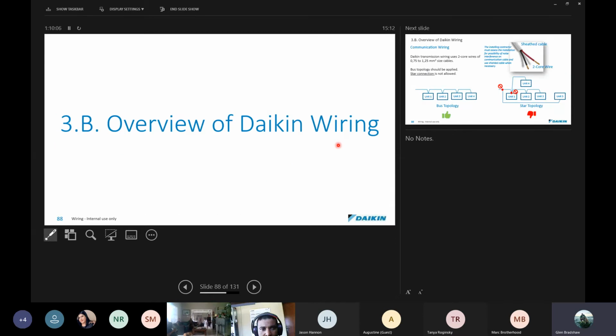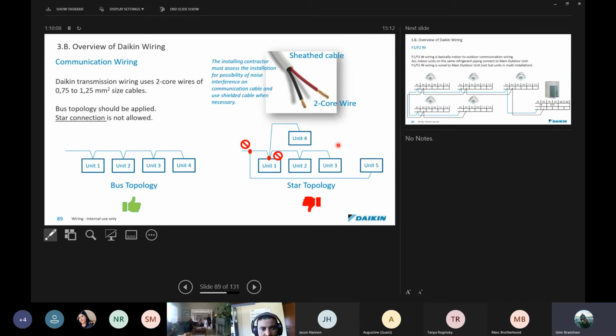Overview of the Daikin wiring. Okay. Daikin transmission wires use 2 core cables. They must be between 0.75 and 1.25 millimeter square cables. Okay, here we're talking about the communication wiring. And the bus topology should be applied. Star connections are not allowed. In other words, it must go daisy chain as we talk about it. You may not star off and go to another unit.